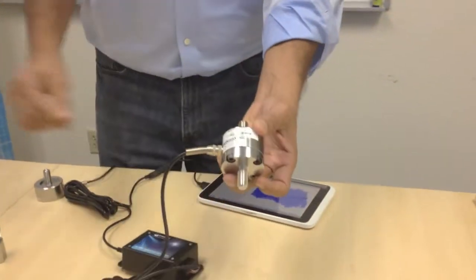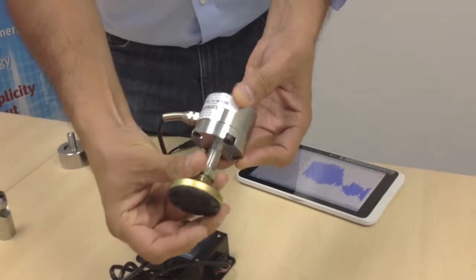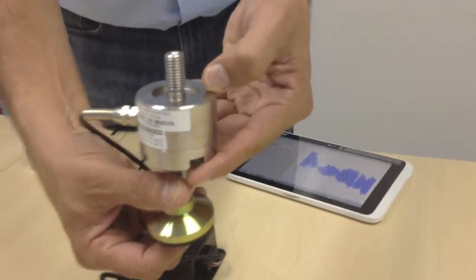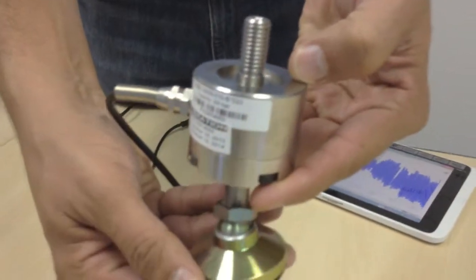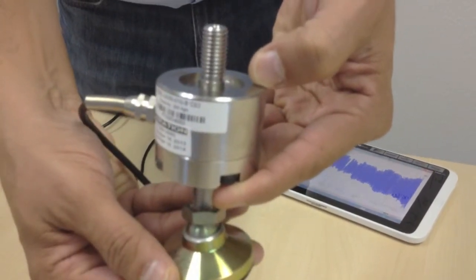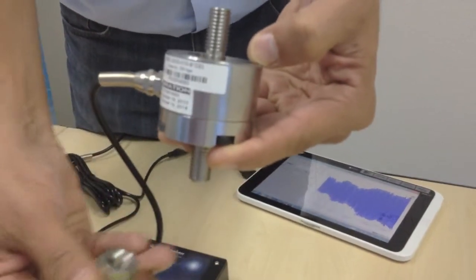Another thing I wanted to show you here is this sensor. You can actually attach a leveling foot to it. By attaching a leveling foot to it you can use these sensors at the four corners of a frame or of a plate and just make a very quick scale. So you can use four of these load cells at four corners with these leveling feet to adjust the level of the scale.